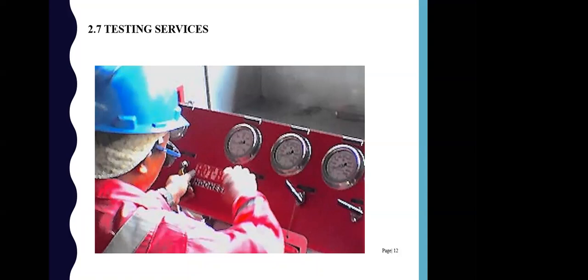The difference between testing and inspection: inspection is witnessing the installation work and completion during execution. After you complete the installation, you have to test it to check if it is performing well or not. Testing is mainly for the equipment. For systems, we cannot test partially; testing is mainly for integrated systems, once you complete a major part of the system installation and connectivity.